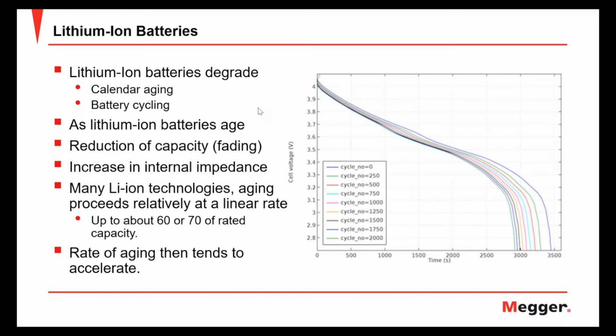Now, lithium-ion batteries degrade both by calendar aging and battery cycling. Okay, both of them lead to aging. As they age, the SEI buildup gets larger and larger. This reduces the capacity of the battery and is often referred to as fading. As this happens, the internal impedance of that battery rises. Now, for many of the lithium-ion technologies out there, you're going to see a relatively linear rise in that impedance until you reach about 60 or 70% of its rated capacity. When it passes that point, the impedance will start going up at a more dramatic rate.